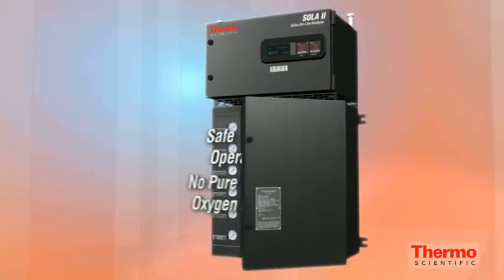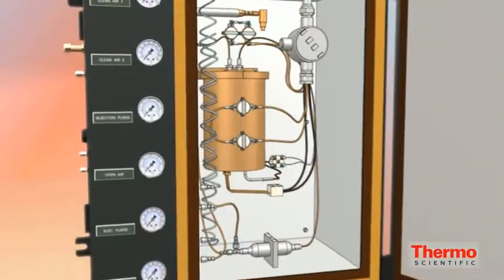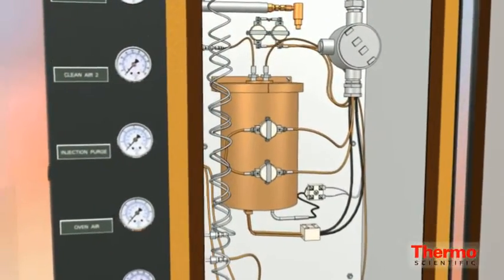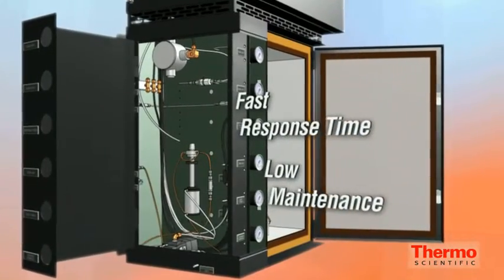The SOLA-2 ensures safe operation in hazardous areas because pure oxygen is not required for sample combustion. This value is delivered through very fast response times and low maintenance demands.